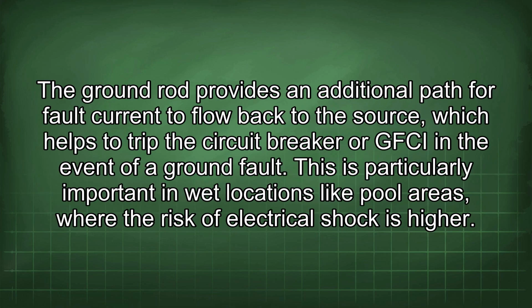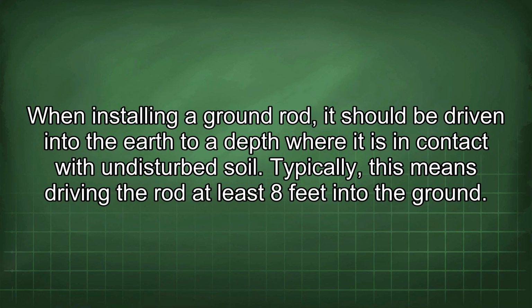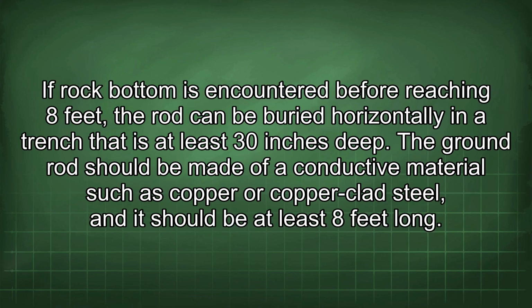The ground rod provides an additional path for fault current to flow back to the source, which helps to trip the circuit breaker or GFCI in the event of a ground fault. This is particularly important in wet locations like pool areas, where the risk of electrical shock is higher. When installing a ground rod, it should be driven into the earth to a depth where it is in contact with undisturbed soil. Typically, this means driving the rod at least 8 feet into the ground. If rock bottom is encountered before reaching 8 feet, the rod can be buried horizontally in a trench that is at least 30 inches deep.